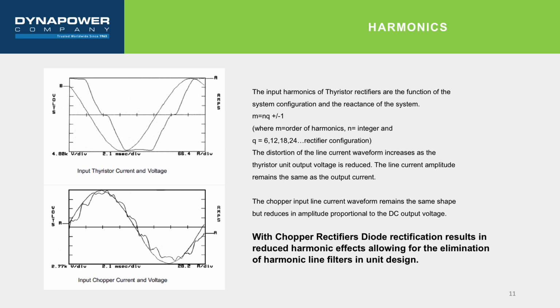The chopper system provides a regulated DC output under large line variations, while maintaining low harmonics, allowing for the elimination of harmonic line filters in unit design and providing the ability to meet the harmonic limits of IEEE 519, the standard for recommended practice and requirements for harmonic control in electrical power systems, without these filters.